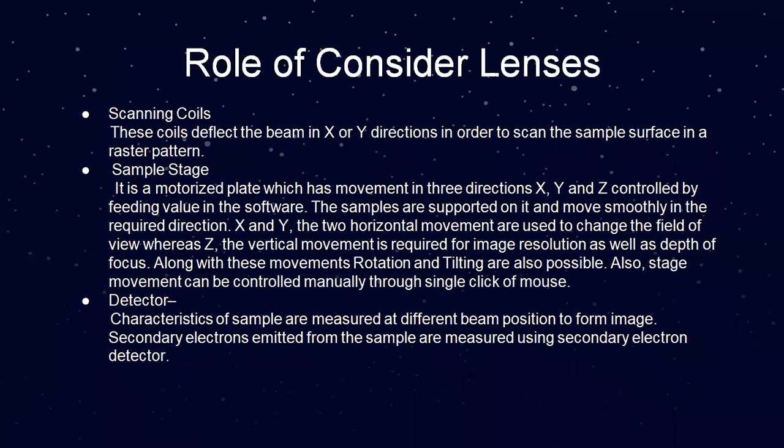Next, I will explain the roles of scanning coils, sample stage, and detector. First, scanning coils: these coils deflect the beam in the x or y direction in order to scan the sample surface in a raster pattern. Second, sample stage: it is a motorized plate with movement in three directions — x, y, and z — controlled by input values. The samples are placed on it and move in the required x and y directions; the two horizontal movements change the field of view, while z (vertical movement) is required for image resolution and depth of focus. Rotation and tilting are also possible, and stage movement can be controlled manually with a single click of the mouse. Third, detector: characteristics of the sample are measured at different beam positions to form an image. Secondary electrons emitted from the sample are measured using the secondary electron detector.